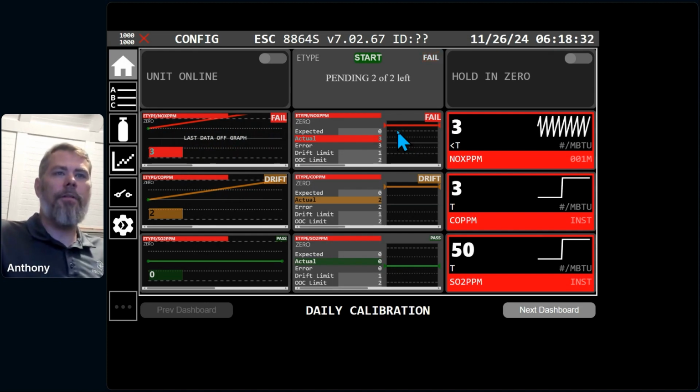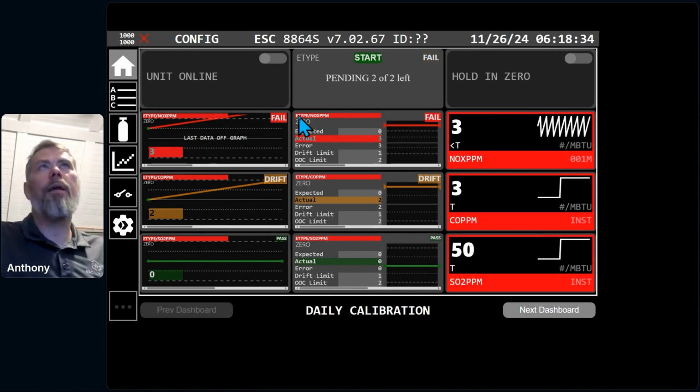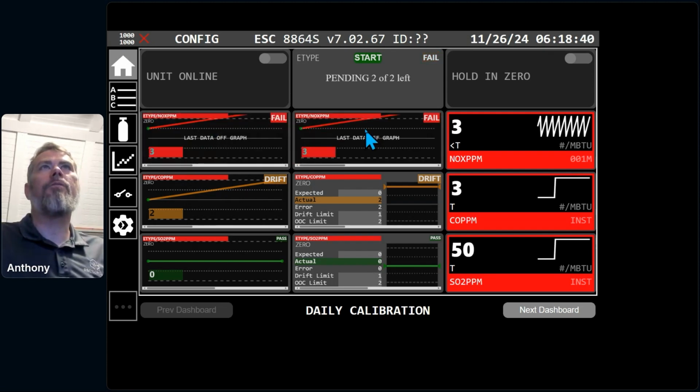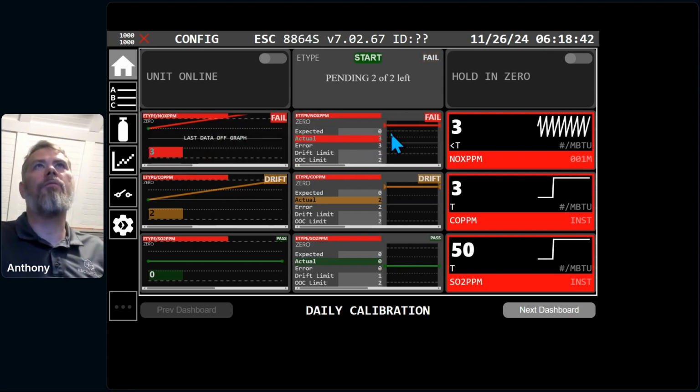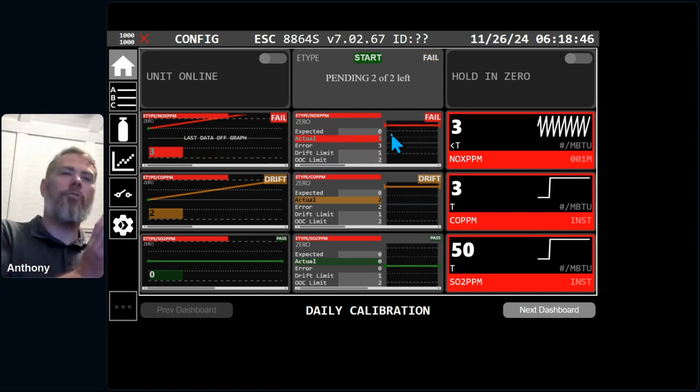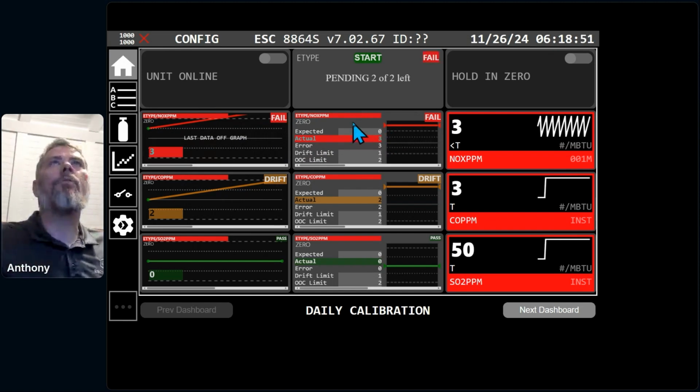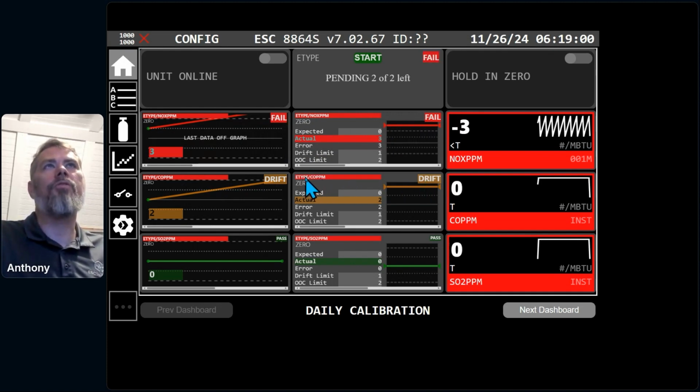However, the detail view is a little bit different. Again, we have the calibration and channel name, and you can switch back and forth between these two by double-clicking on them. So if you only wanted to take up the space of one, you could see your trend, and then you could go look. The difference is the trend shows you multiple runs, whereas the detail view shows you just one run. And so here on the detail view, we have the same thing. We have the current phase's status. You can see here's the drift, where we see a red for worst status of the whole cal, and the phase name.